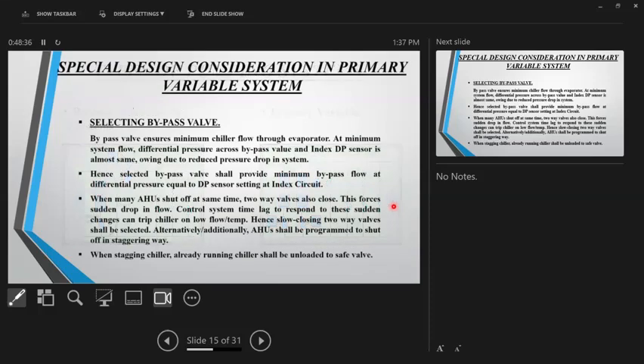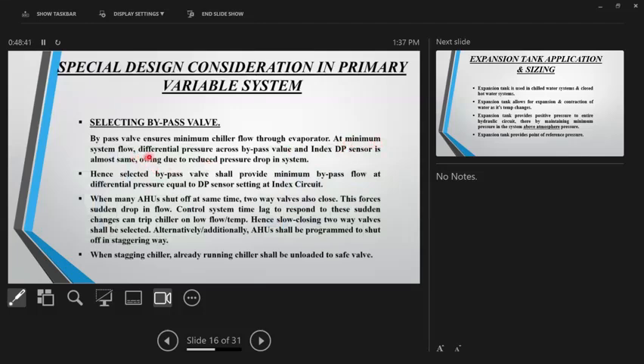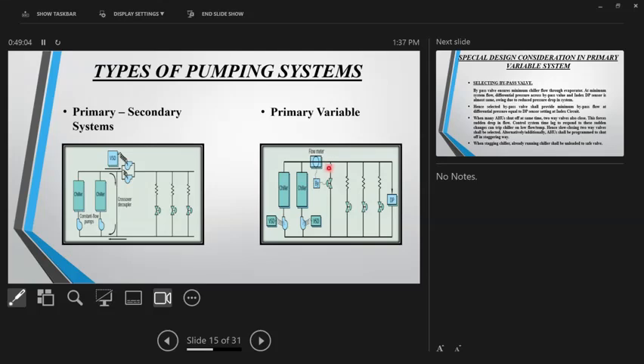Okay, so I'll go back again. Now it will make sense to you. At minimum system flow, differential pressure across bypass valve and index DP circuit is almost same owing to reduced pressure drop in the system. Hence, selected bypass valve shall provide minimum bypass flow at differential pressure equal to DP sensor setting in index circuit. Again, let us go back. Now, what is the minimum flow through this? What it says is the pressure drop across this valve at minimum flow should be equal to your delta P setting. The minimum flow through this line is how much? The minimum flow produced by the chillers, minus the minimum flow through the load. The remaining will be bypassed.